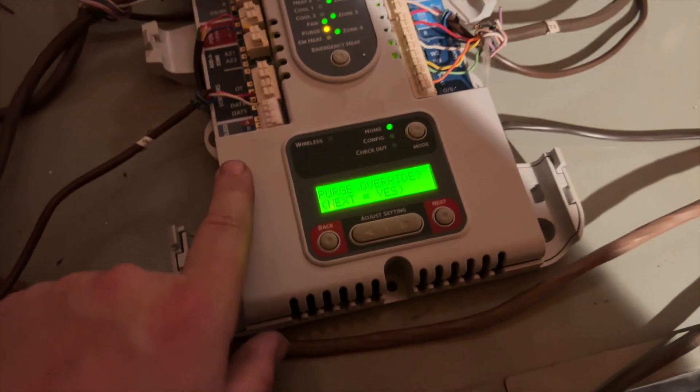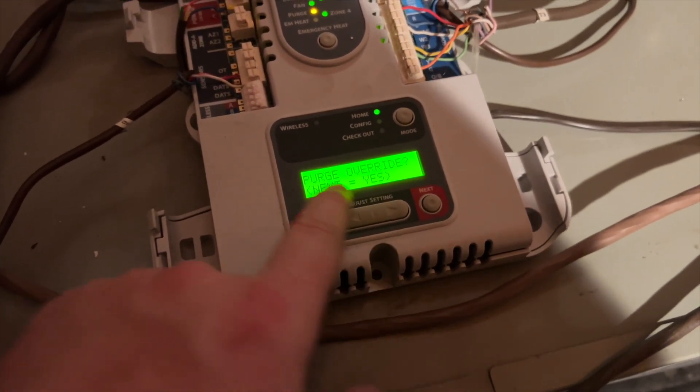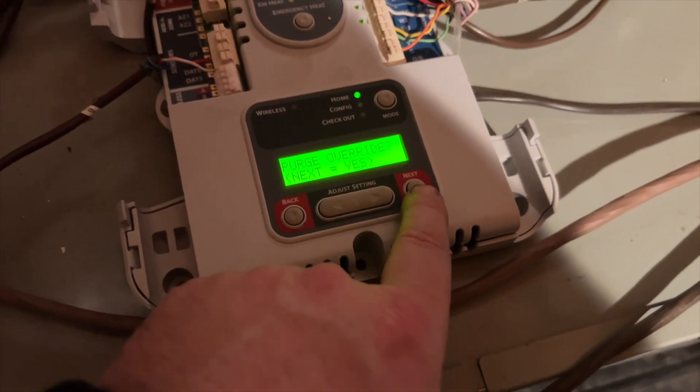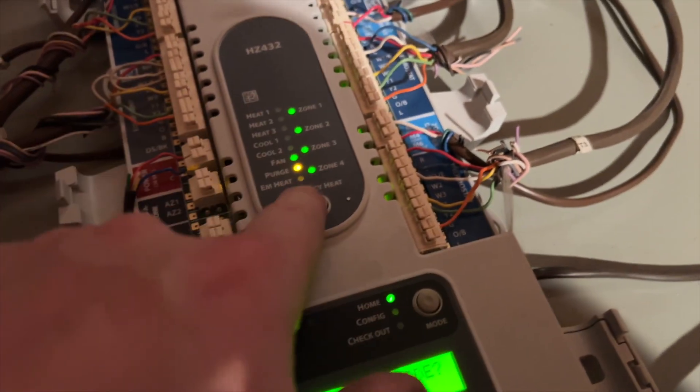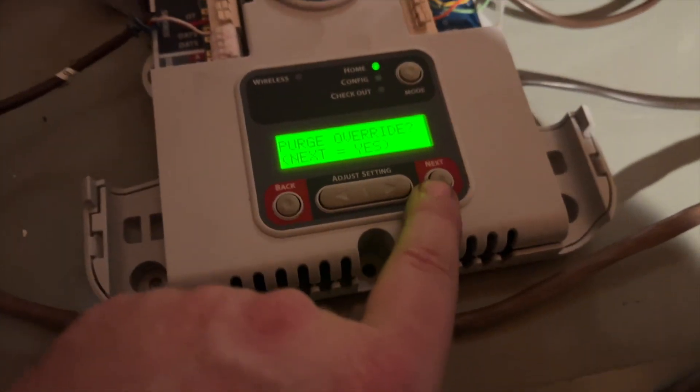So now it's in a purge. If we want to override it, we can just hit the next button and it'll do that. See the yellow light? That means it's a purge and it's calling for fan and it's opening all the dampers as per our settings. So we'll go ahead and skip that. Now you can see the fan shut off and now it's back to receiving the calls from the stats.